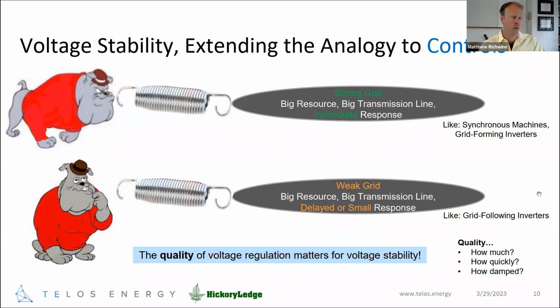What this boils down to is that it's the quality of voltage regulation that matters for voltage stability. When we talk about voltage stability and grid strength, we've customarily focused on metrics like short circuit strength or short circuit ratio. That accounts for some of it, but not necessarily the quality of the voltage regulation being provided. By quality, I mean how much effort is being applied, and how quickly that effort is applied.